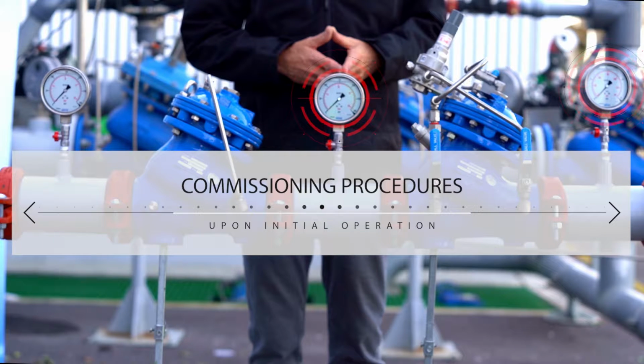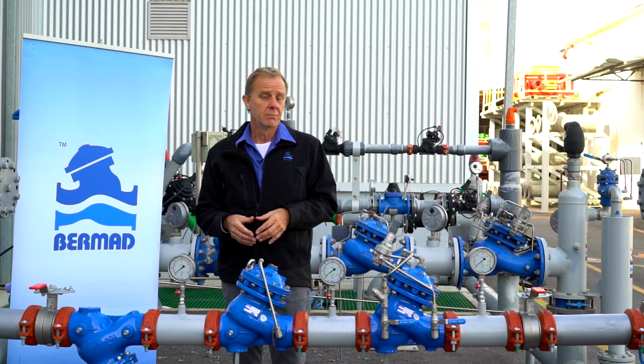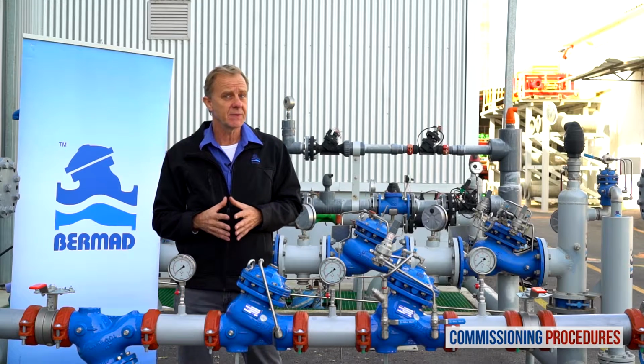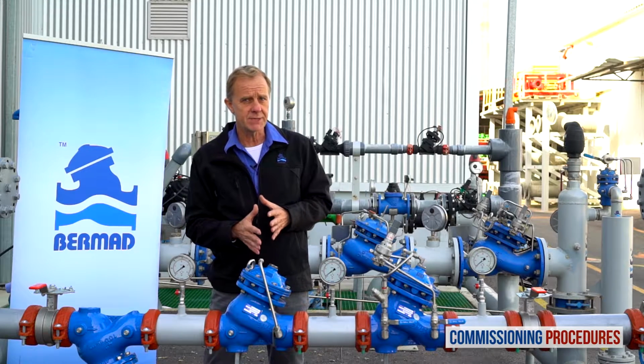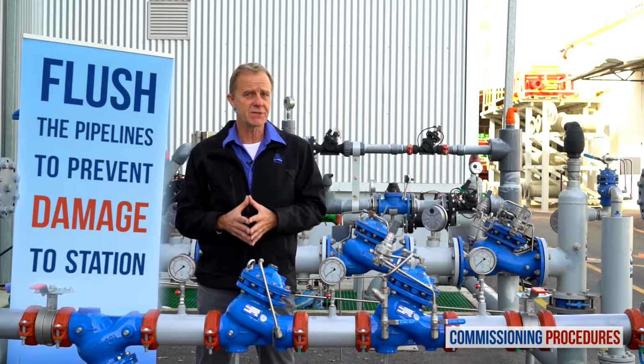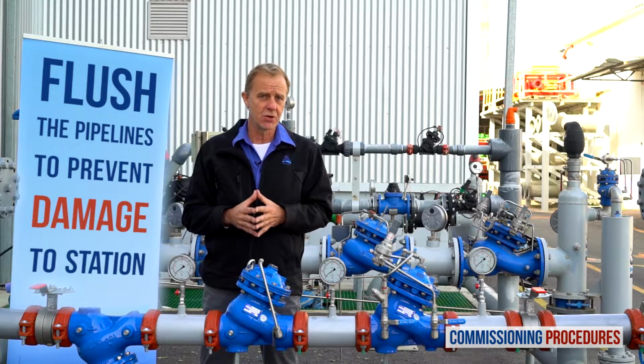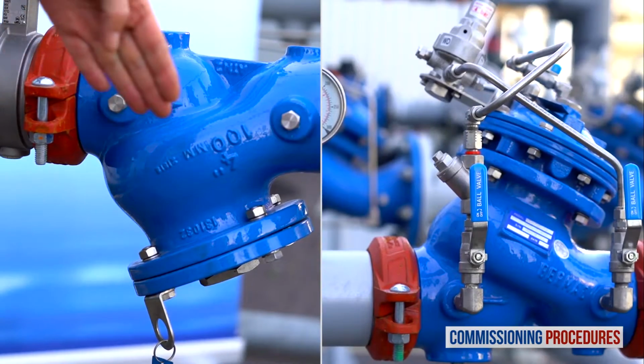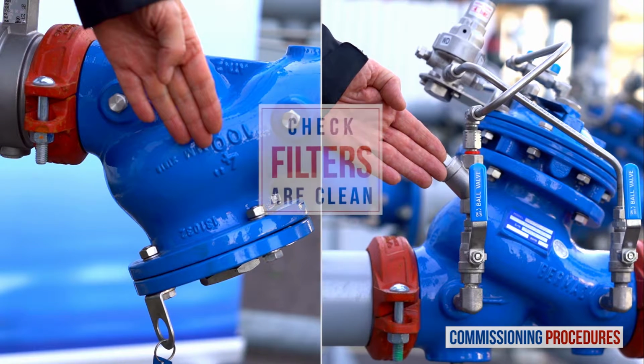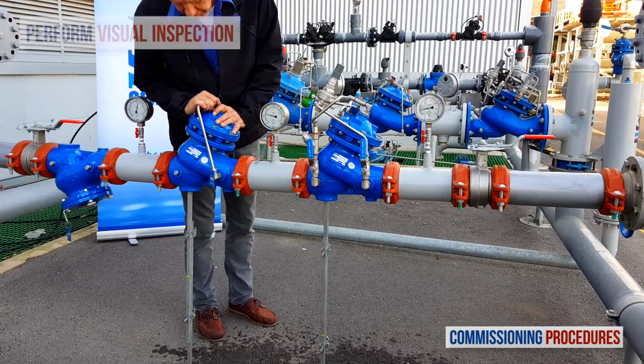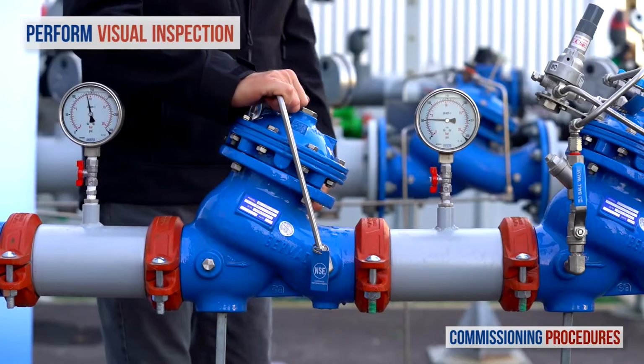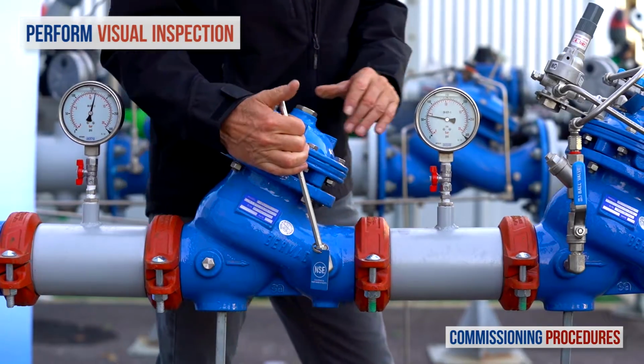Commissioning procedures should be performed when initially opening and operating a station, either for the first time as a new installation or after intrusive system maintenance. Before operating the system for the first time, it is imperative to flush the pipelines. This ensures that the system is free from any debris that can cause damage or even render it inoperable. After flushing, ensure that the main strainer and valve's control loop filters are clean. Next, observe the station's installation and make sure that all parts are firmly secured and in place.